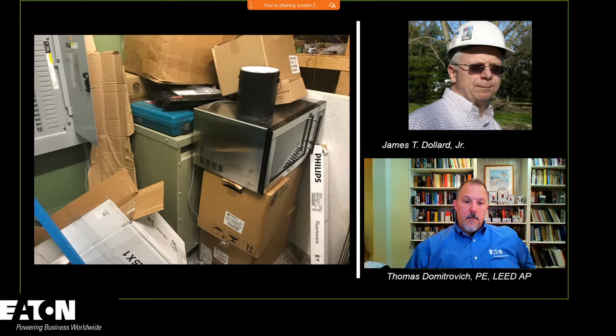It has nothing to do with an arc flash boundary - it never did. It's just a minimum amount of space for me to get in there and work on the equipment. The other thing workspace clearances ensures, when we follow all those requirements, is that I don't have, for example, a panel board above a transformer. If I did, I'd literally have to lean on the transformer - lean on grounded metal surfaces - to work in an energized panel board.